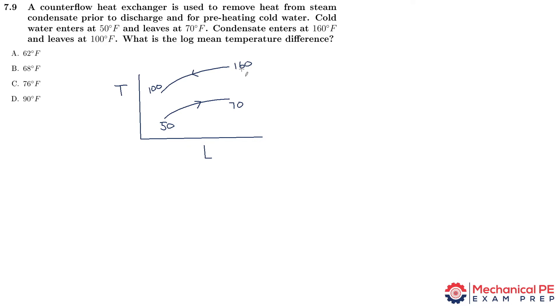The implication for analyzing the performance of any heat exchanger is to find the log mean temperature difference, and that's exactly what we're going to do here. In the same manner as before, once we have this picture, the rest of the process unfolds very easily. I recommend drawing a picture and using this graphical method of calculating LMTD, where you define the left side as 'a' and the right side as 'b', then find delta T_a and delta T_b and use those in the calculation.